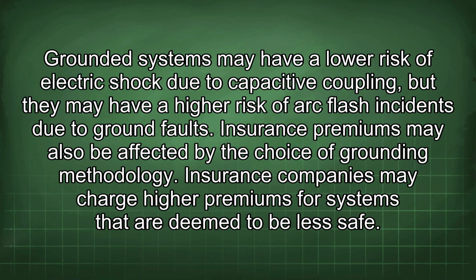Grounded systems may have a lower risk of electric shock due to capacitive coupling, but they may have a higher risk of arc flash incidents due to ground faults. Insurance premiums may also be affected by the choice of grounding methodology. Insurance companies may charge higher premiums for systems that are deemed to be less safe.